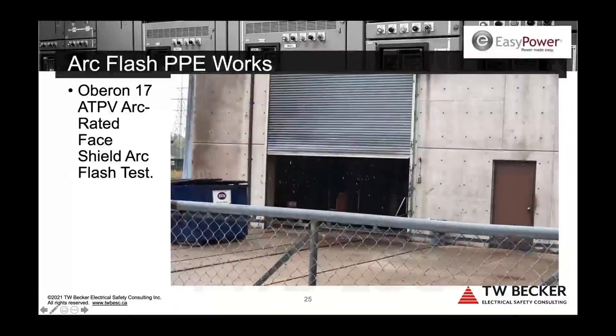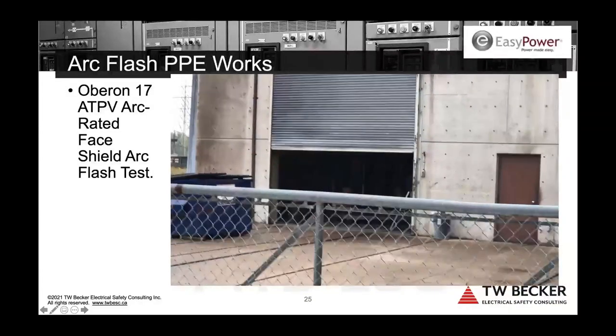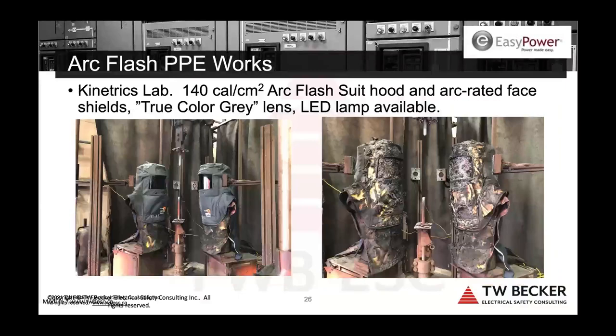So that was probably a 20 cal, because the shield's rated to 17 cals per centimeter squared ATPV. And sometimes when I show these videos, I have to temper them: at the labs, they play around with the fault current and the time to get the incident energy. You know the calculations. So sometimes the arc flash you see isn't what we would expect in the field. They won't be sustained that long, right? So I just temper that.